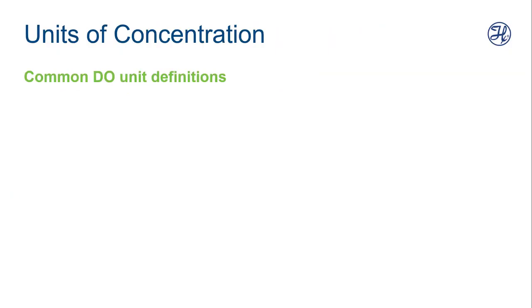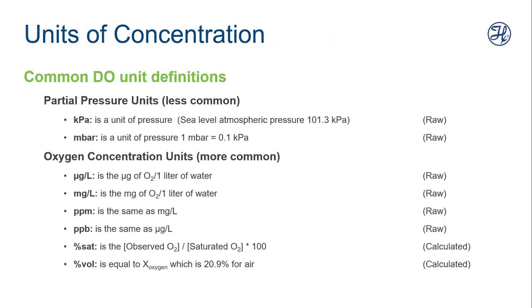So with that said, keep that in mind that we have these units of measure, and that some of these units of measure use a calculated value, and some of the units of measure use the raw partial pressure measurement off the sensor. Both are correct. But you need to be aware that the calculated value is using an atmospheric pressure value that is stored in the sensor. And if you were at a higher or lower atmospheric pressure, you need to adjust that for where you're at.